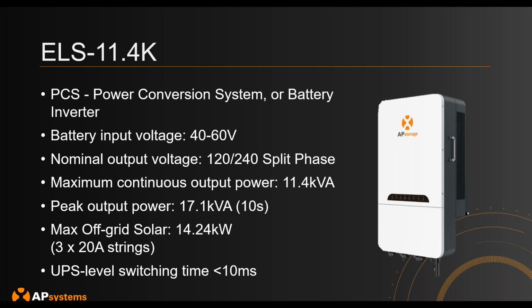If you want to add additional batteries, it's possible to put them in parallel to give the system more time to stay on backup. The nominal output of this inverter is 120/240 split phase natively. Continuous power is 11.4 kilowatts, and peak power is 17.1 kilovolt-amps for 10 seconds. The maximum solar you can charge when you lose the grid is 14.2 kilowatts on the AC side, corresponding to around 3 strings at 20 amps. Another nice feature is the uninterrupted power supply switching time is very fast.